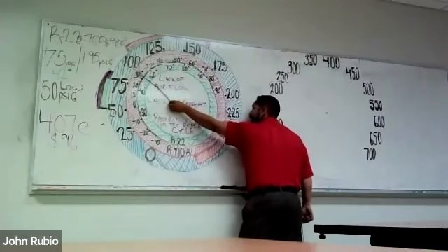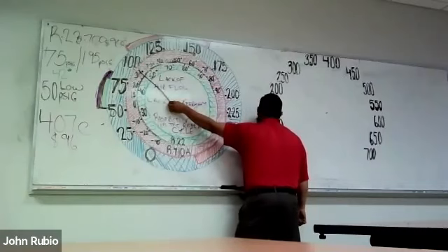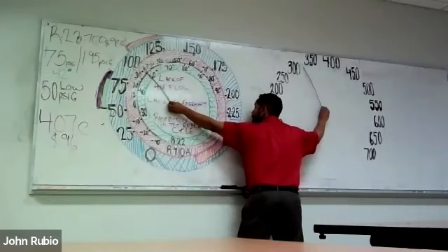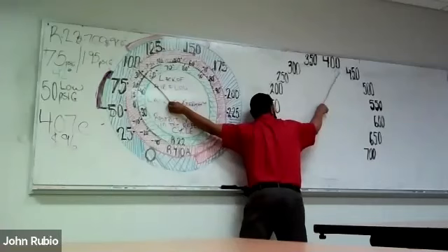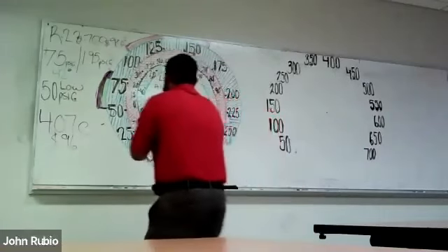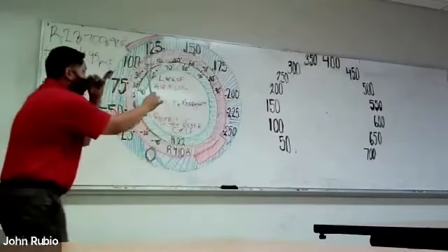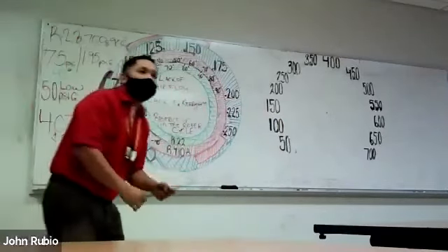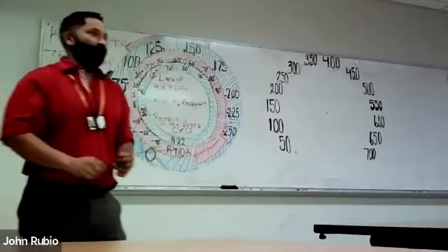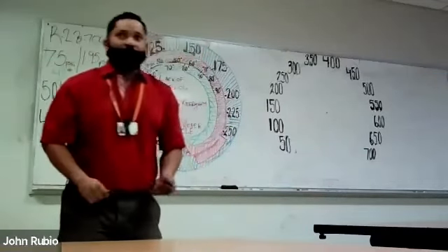What's going to happen is you're going to add gas and add gas and add gas, and it's going to keep going down because the refrigerant you're adding may register. But as the restriction gets stopped, it starts to register only in the high side. This is a restriction. You will have this lack of congruency with your needles when you're truly restricted, or if there's ice on the evaporator coil. Systems freeze up.